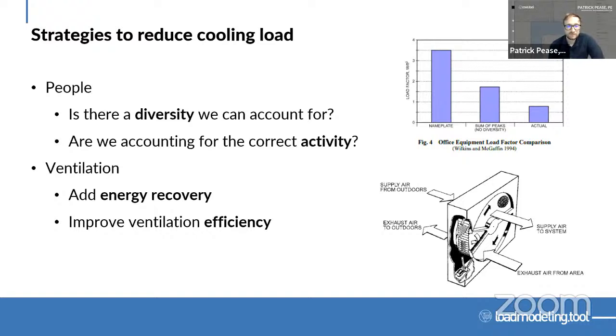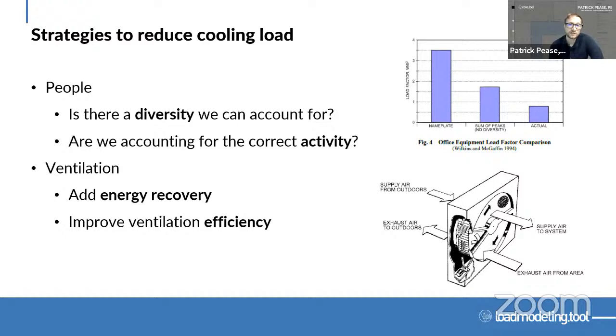For ventilation, number one — very common in most codes now — is to add energy recovery. By adding energy recovery, we're essentially transferring heat from the already-conditioned air in the building to the incoming outdoor air, and we can save a lot of load that way. Another more nuanced approach is to look at ventilation efficiency under ASHRAE 62.1's ventilation rate procedure. If we can adjust the design to have a better ventilation efficiency — for example, delivering air more effectively to occupants — we can actually reduce the outdoor air required to be delivered, thus reducing the ventilation load.